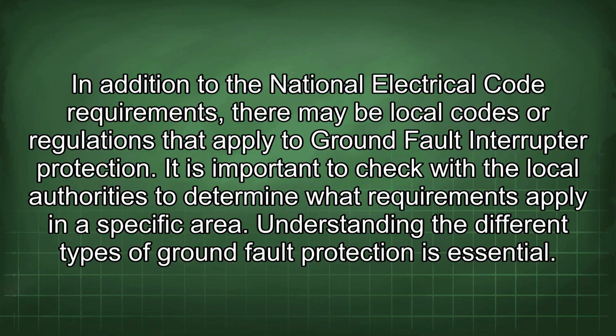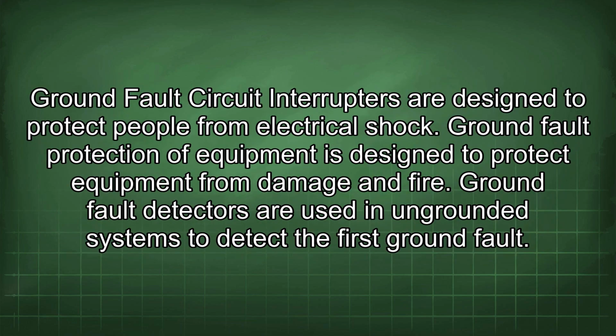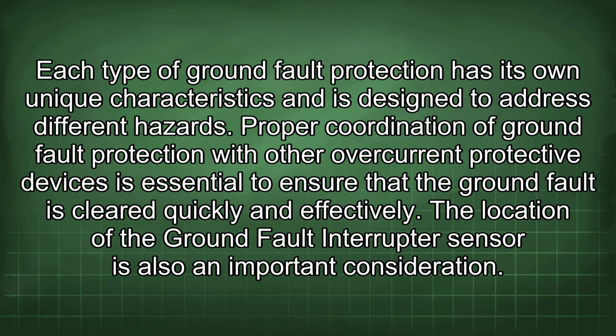Understanding the different types of ground fault protection is essential. Ground fault circuit interrupters are designed to protect people from electrical shock. Ground fault protection of equipment is designed to protect equipment from damage and fire. Ground fault detectors are used in ungrounded systems to detect the first ground fault. Each type of ground fault protection has its own unique characteristics and is designed to address different hazards.